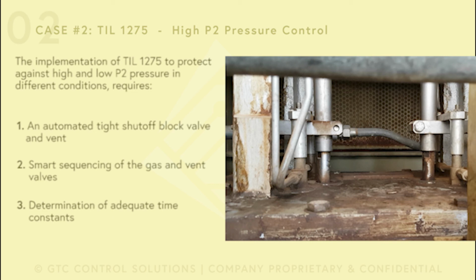So this is what we did. We staggered the valves safely so there will be no gas going into the unit without spark plugs, the igniters, on. And the sequencing created first opens the gas control valve, the stem on the right, then you'll hear a whoosh, which is the block valve opening, and last, the speed ratio valve opening. And in this case, after the modification, the P2 pressure was exactly 25 psi, and the speed ratio valve opened only 0.8%. Let's see the video.